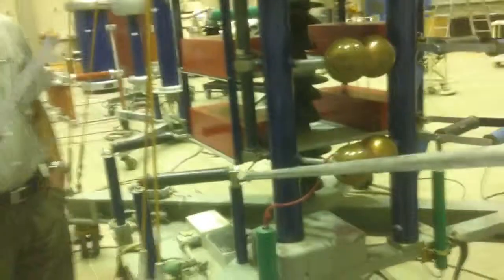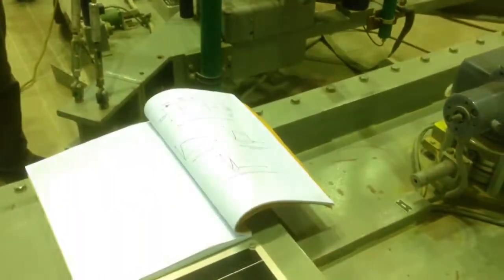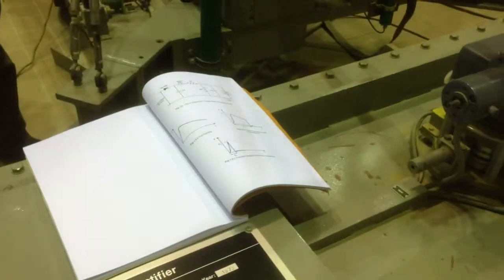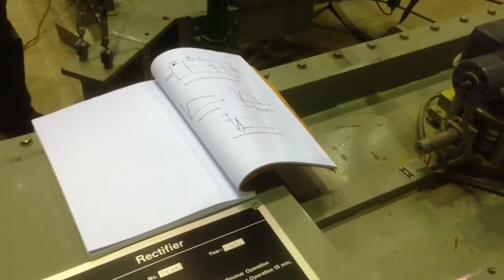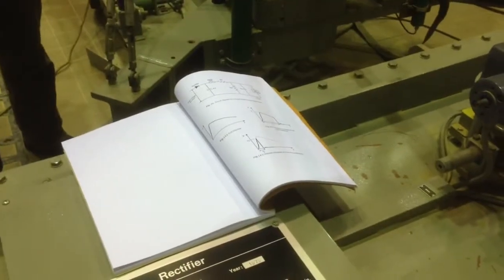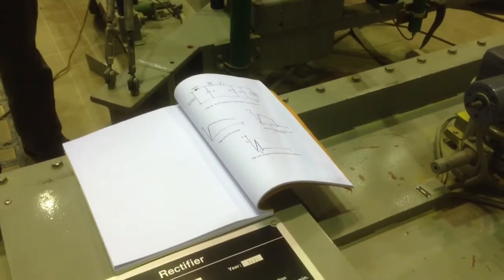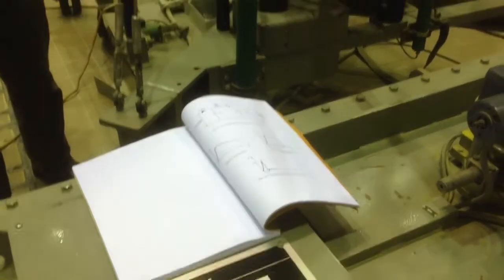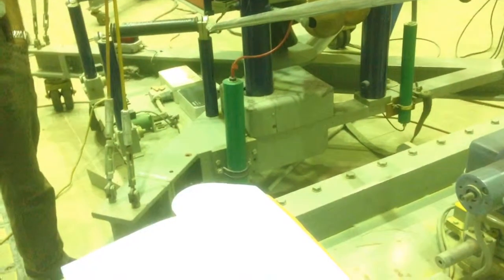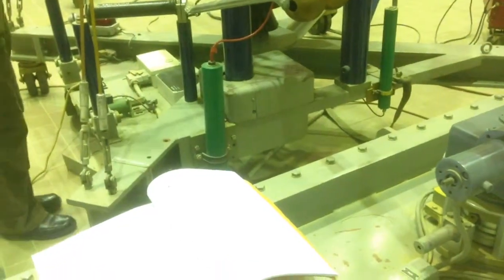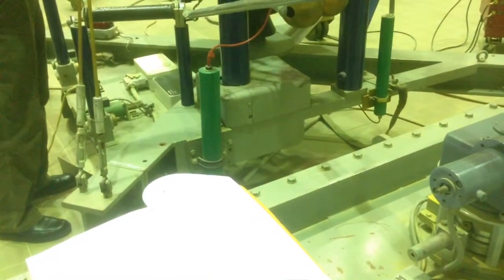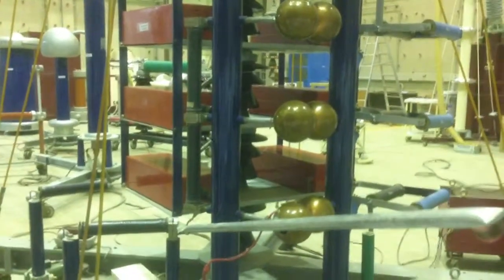Now you have ten stages like this: 1, 2, 3, 4, 5, 6, 7, 8, 9, 10. Each stage is 100 kilovolt, so we get a maximum up to 1 million volt. Now depending on your voltage, how many stages do I need? Maybe 200 kilovolt needs 2 or 3 stages. Say I need around 150, 160 kilovolts, so I connect only 3 stages. So charge goes to the first stage, second stage, and third stage, and the rest is all open. The maximum I can get today is 300 kilovolt.